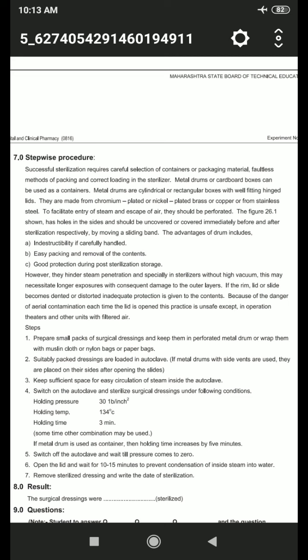Then step one: prepare small packs of the surgical dressing and keep them in a perforated metal drum, or wrap them with muslin cloth, nylon bags or paper bags. Then suitably packed dressings are loaded in the autoclave. That is, if metal drums with side vents are used, they are placed on their sides after opening the slides. Then the next step is to keep sufficient space for easy circulation of steam inside the autoclave.